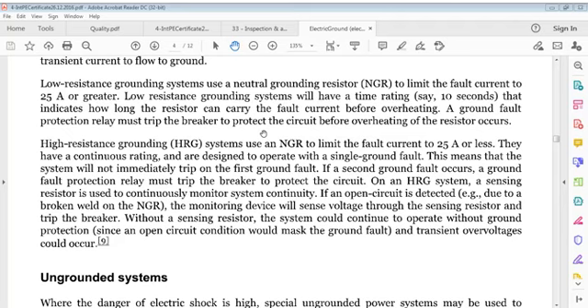On an HRG system, a sensing resistor is used to continuously monitor system continuity. If an open circuit is detected due to a broken weld on the NGR, the monitoring device shall sense voltage through the sensing resistor and trip the breaker. Without a sensing resistor, the system would continue to operate without ground protection, since an open circuit condition would mask a ground fault and transient overvoltage could occur.